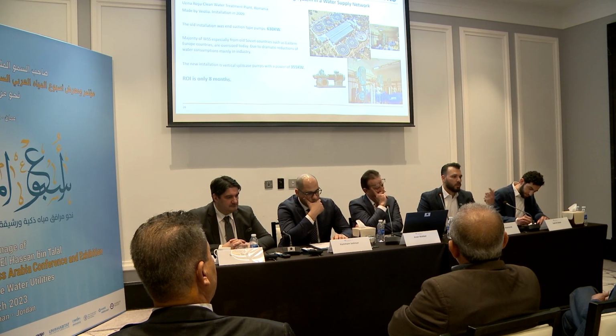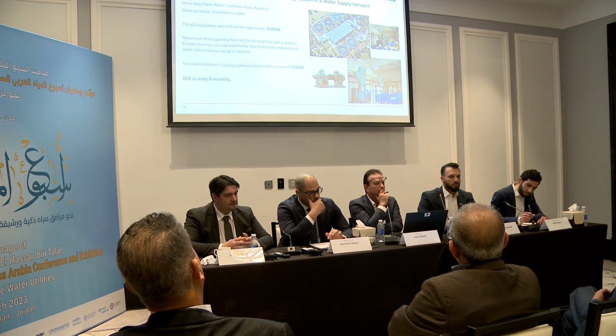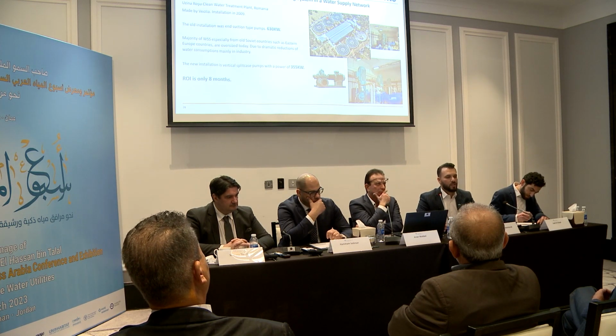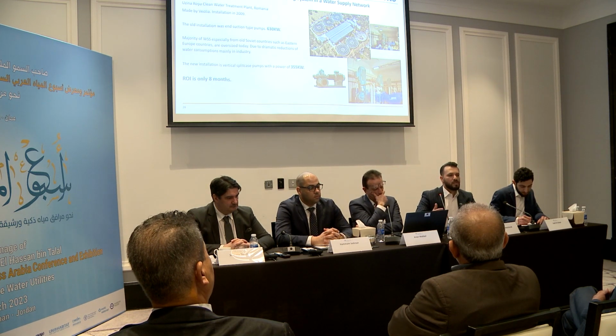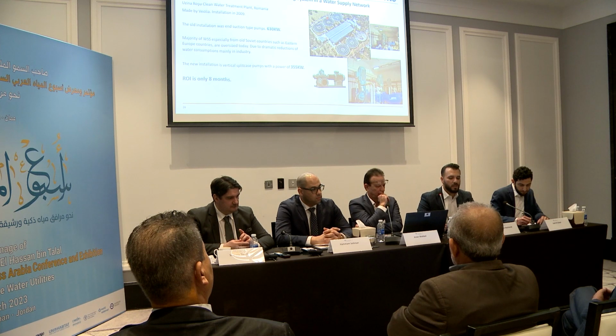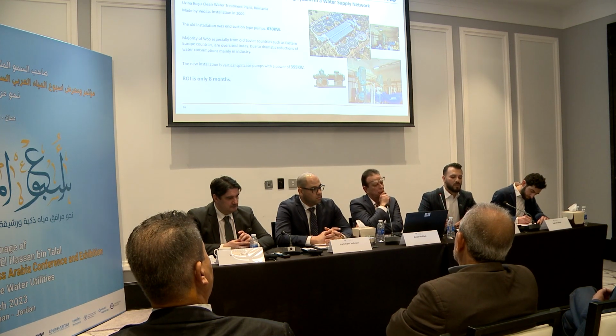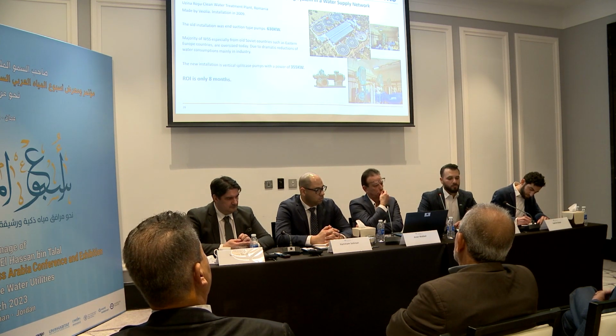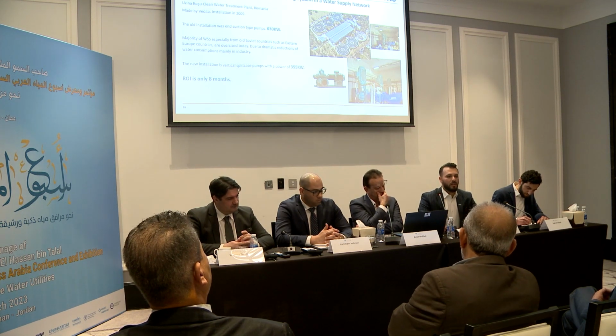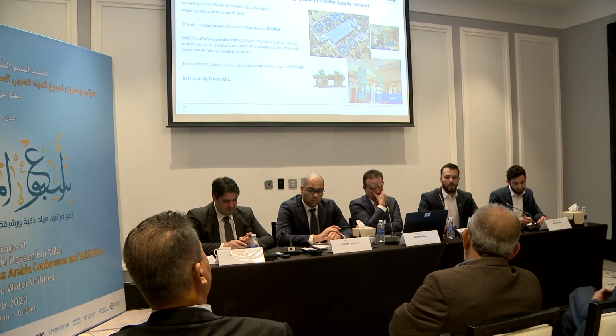Another point is reviewing your system data, inputs, and demands. This is an example for a treatment plant done by Veolia, where because of reduction in industry and water demand, they were running old suction pumps at 630 kilowatts but didn't need that much flow rate and head. When replaced with a vertical split case sized to current demand, there was a reduction of 355 kilowatts, which paid back the investment after 8 months. So we have to really review our system as a complete system.